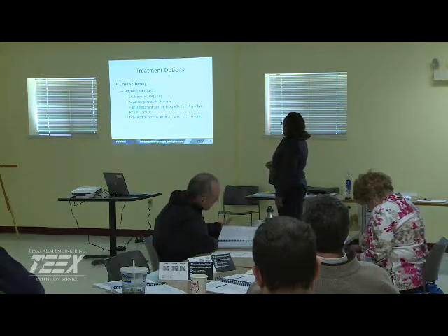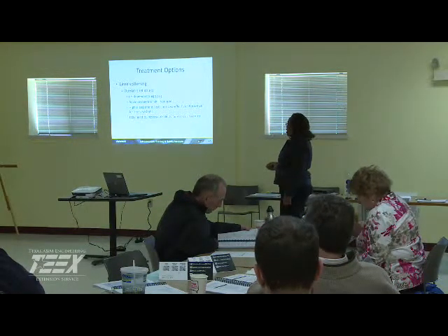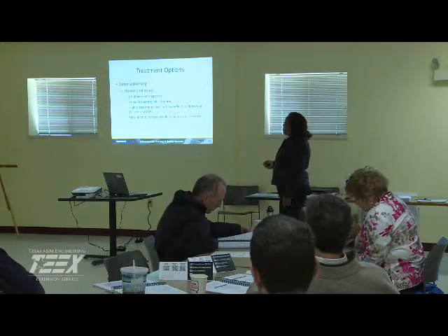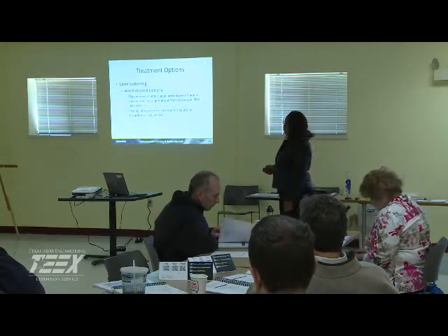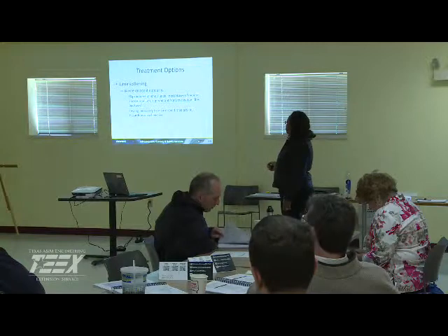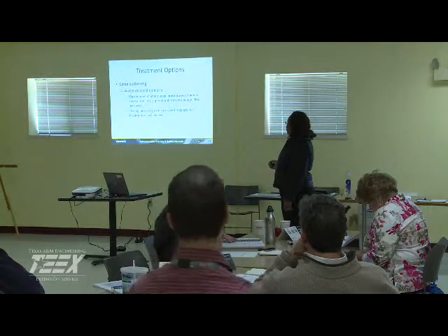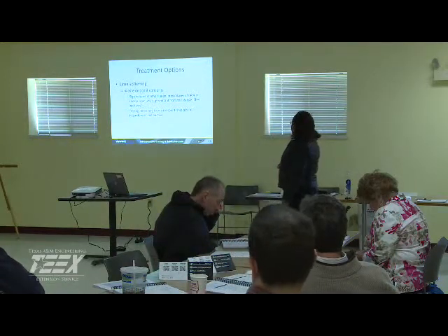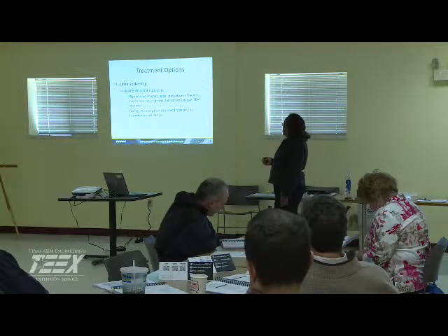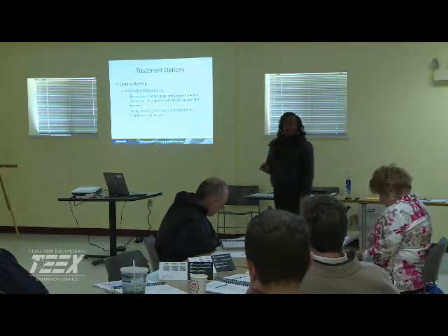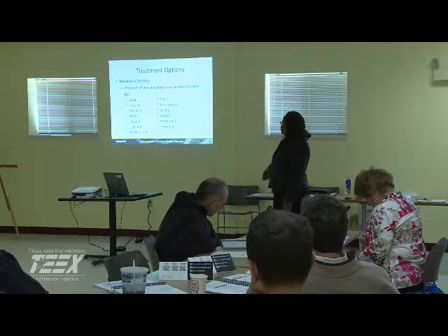Okay, this is a higher treatment cost, so it may not be cost effective for your small systems, and you may need to increase alkalinity for corrosion control if this is one of the plausible options to go with. Again, we're concerned with disposal because we've got a high volume of lime sludge. You could have precipitates of radium or uranium, supernatant from the sludge, or filter backwash. You have to make sure you know what you're going to do with all of that. Again, you want to make sure you're testing to see what's in all of the waste.